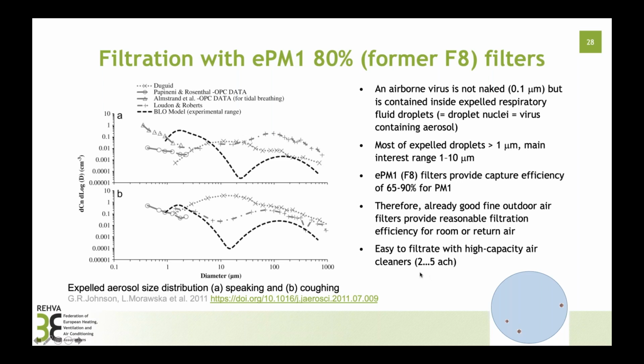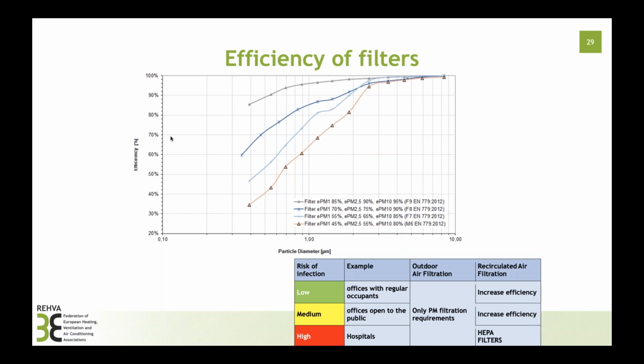And indeed, this means that the virus is easy to filter also with high capacity air cleaners, where you just need to have enough airflow rate. So room air cleaners will also benefit from the fact that we are filtering quite large solid particles in this case. And HEPA filters are basically not needed even when we speak about public buildings. But indeed, when we go to a hospital setting, where you need practically 100% filtration, and when F8 or F9 type filters are not enough, then HEPA filters should be applied. But in common spaces, yes, all these common filters, so these old F7, F8, F9, are highly useful for filtration purposes, and the same also applies for air cleaners.